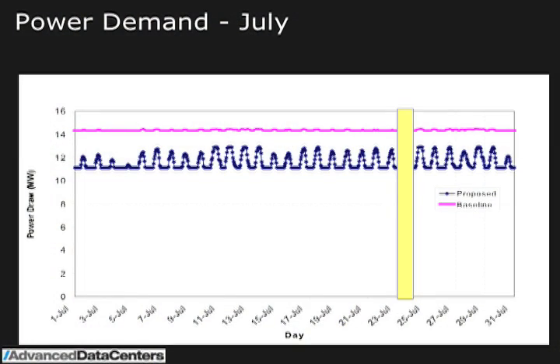Here's the month of July. You can see during July, which is one of the hot months, during the day the chiller's coming on, but at night we're able to do full economizing. That's because in Sacramento, when it's 100 degrees during the day, or let's say 90 degrees during the day, oftentimes it will go down into the mid-60s at night. You get a nice big temperature swing here, usually 20 to 30 degrees from daytime to nighttime. So we're going to take advantage of that.